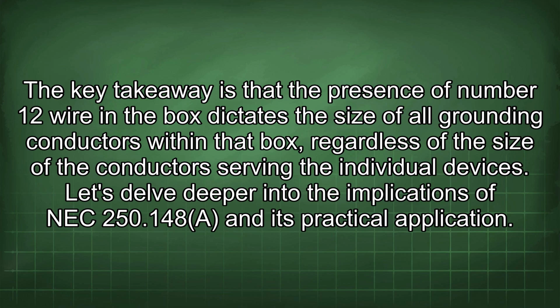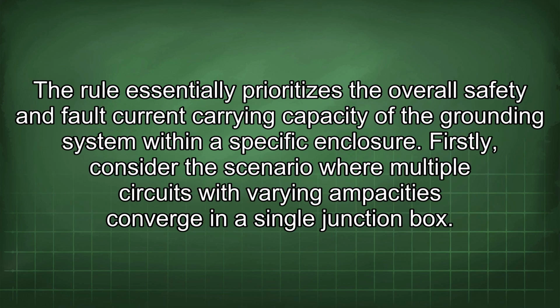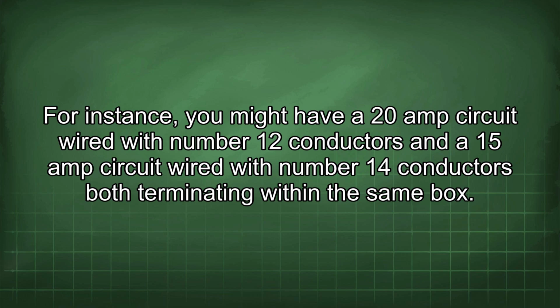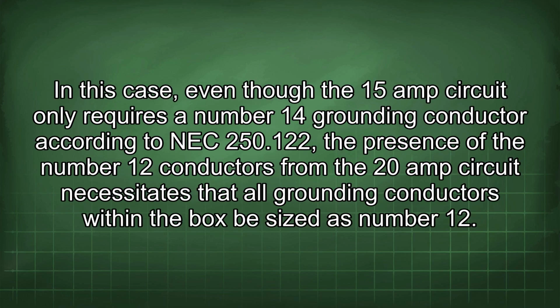Let's delve deeper into the implications of NEC 250.148 and its practical application. The rule essentially prioritizes the overall safety and fault current carrying capacity of the grounding system within a specific enclosure. Firstly, consider the scenario where multiple circuits with varying ampacities converge in a single junction box. For instance, you might have a 20 amp circuit wired with number 12 conductors and a 15 amp circuit wired with number 14 conductors, both terminating within the same box. In this case, even though the 15 amp circuit only requires a number 14 grounding conductor according to NEC 250.122, the presence of the number 12 conductors from the 20 amp circuit necessitates that all grounding conductors within the box be sized as number 12.